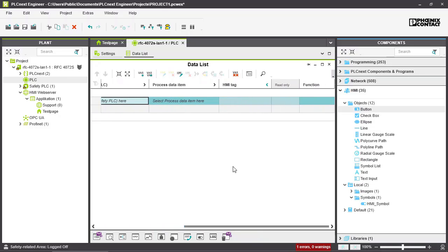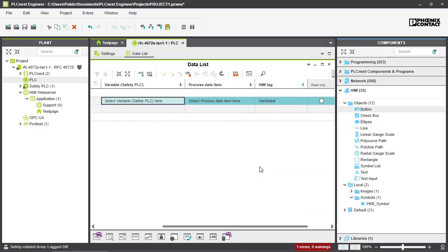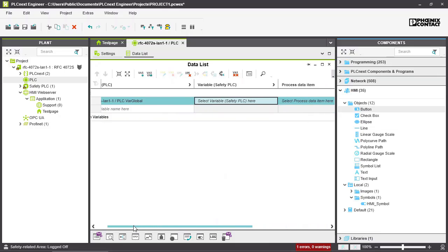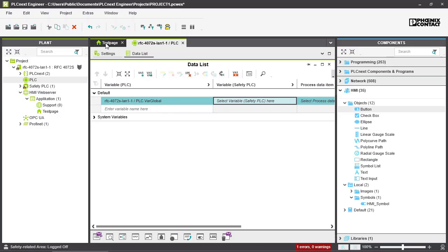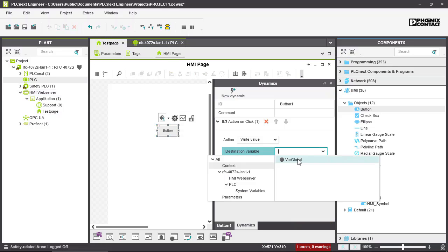To use a global variable in the HMI application, we have to use HMI tags. Go into the HMI tag column, right-click, and select 'Add HMI tag'. This creates its own global HMI tag variable. We can then go back into our test page and select that global variable as our destination.